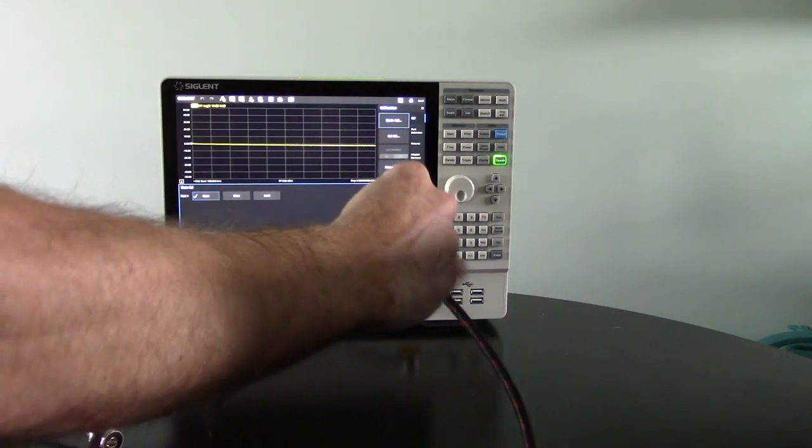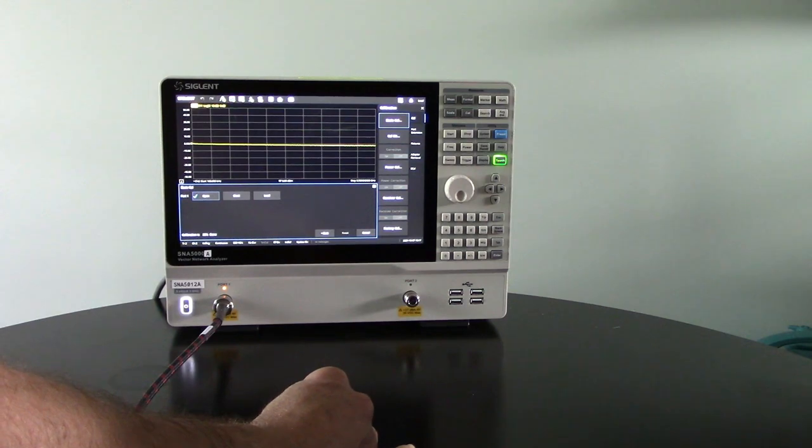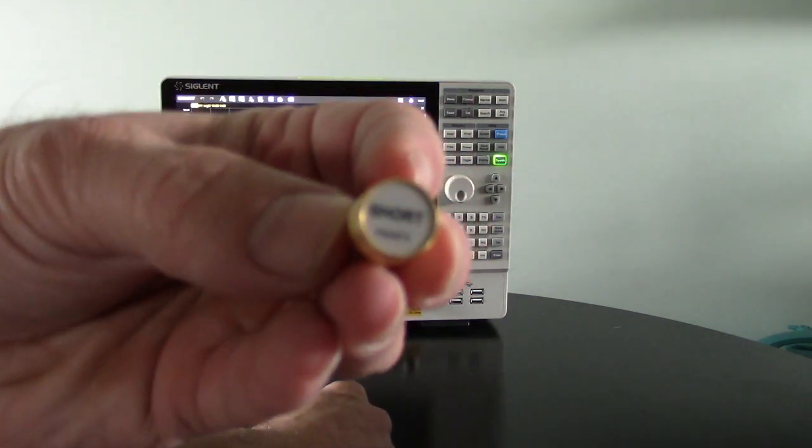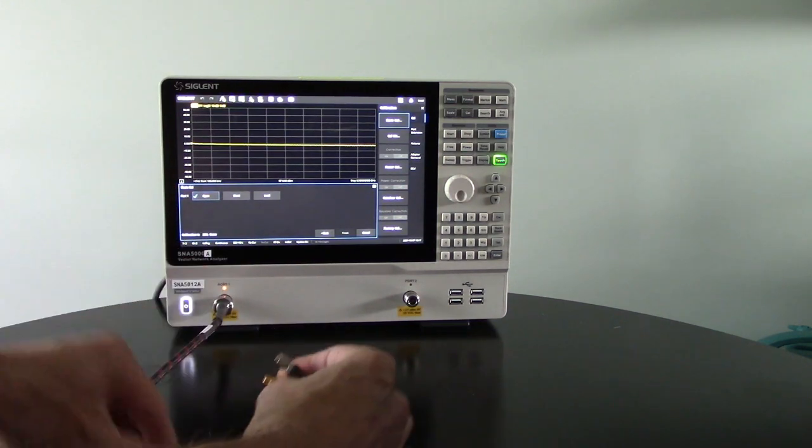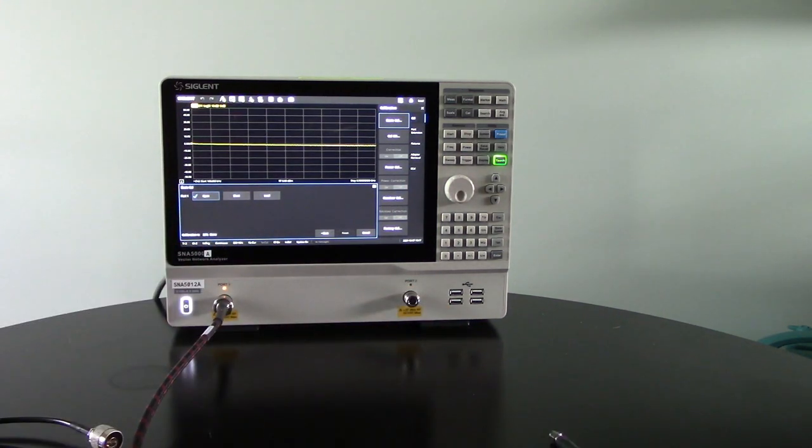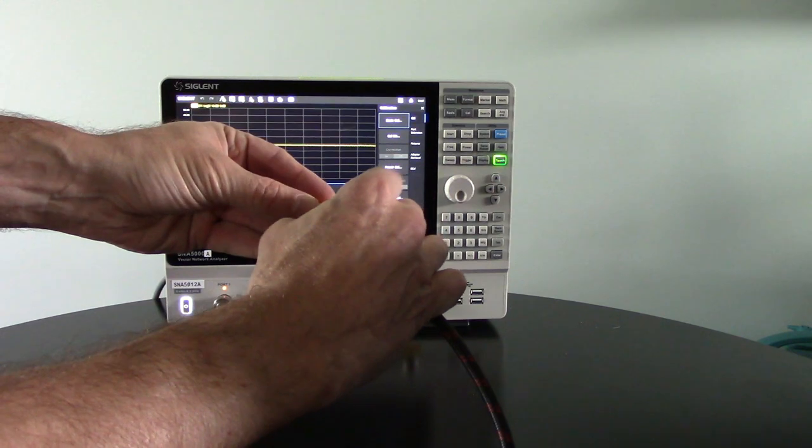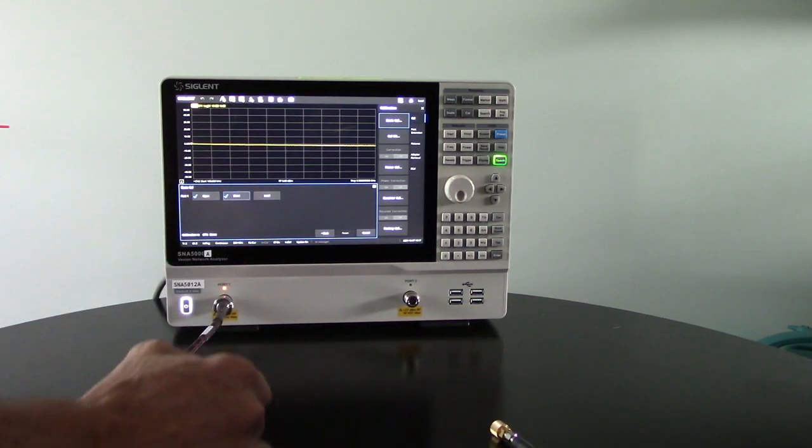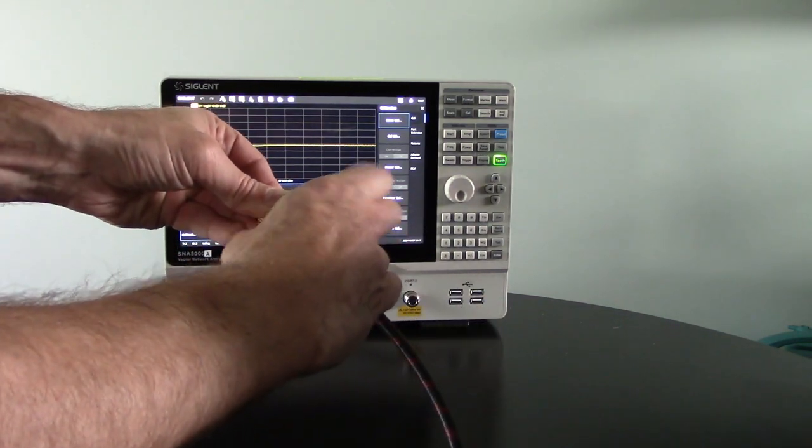Once that calibration is complete, we will unscrew the barrel, remove the calibration element and we're going to move to the short. Here we are with the short and we're going to pull its cap off and give it a quick shot with our compressed air. We will then connect onto the cable, again we're spinning the barrel and tightening. And we're going to then press that short button and we're going to have that calibration saved.